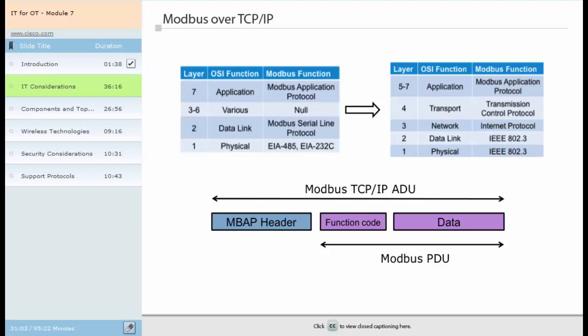Significantly, Modbus is no longer limited to one master with a number of slaves; instead, any number of clients can access any number of servers. A Modbus TCP/IP application data unit, or ADU, consists of the traditional Modbus protocol data unit and a new Modbus application protocol header, shortly MBAP. The function code and data definitions of the Modbus protocol data unit remain intact. TCP uses registered port 502 to send Modbus application data units through the TCP/IP network. Modbus will continue to be popular for its simplicity and the fact that there are many users with Modbus knowledge in the field.